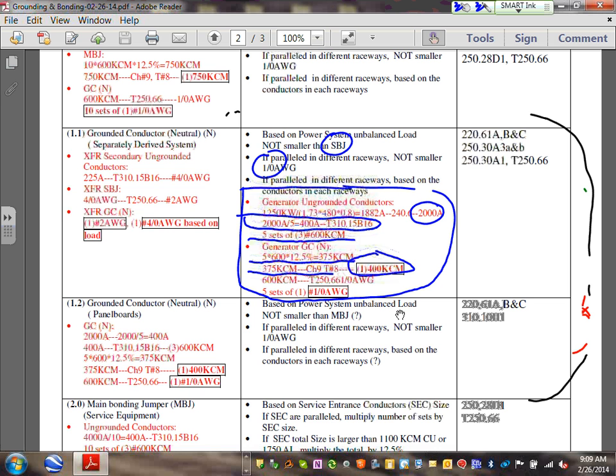There's one little problem, though. What's the problem? I am paralleling at the generator. Because you parallel at the generator, you are to use this method here. You take 600 kcmil to 250.66, and that will get you 1/0. Then I have 5 sets of 1/0 conductors.